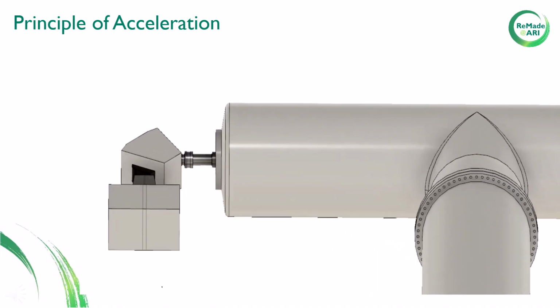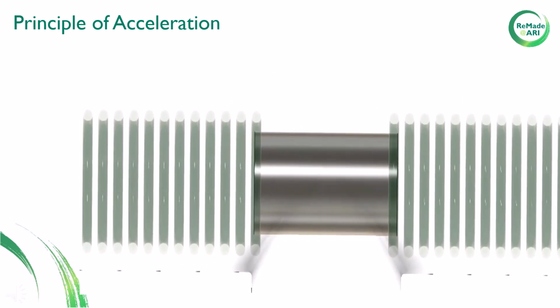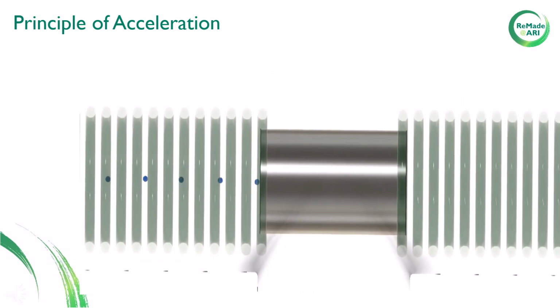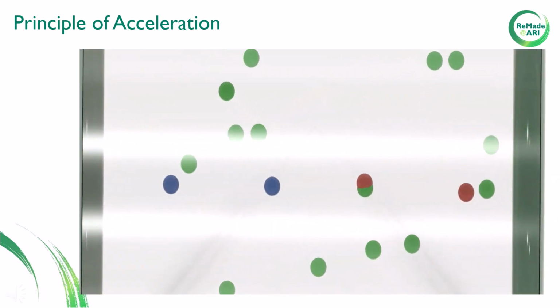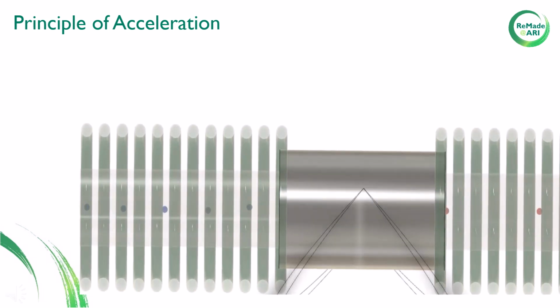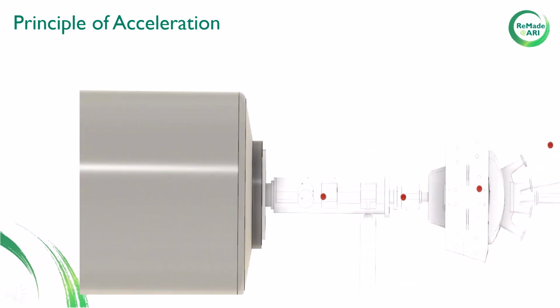From the ion source, the particles move through the ion optics to the magnet. In the magnet occurs the selection of the desired element. From there the ions go to the low-energy part separated from the high-energy part by the high-voltage terminal, where a gaseous stripper is incorporated. The ions lose electrons, and change from a negative to a positive charge state. These partially accelerated ions continue to the high-energy part. The ion beam is directed into a switching magnet, which bends ions of specific charge state and energy into one of 5 defined beam lines and chambers.